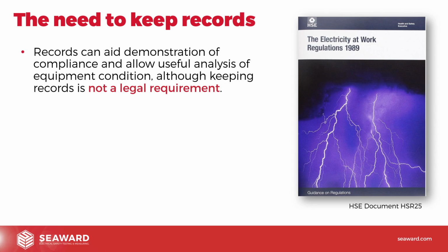The first thing that they explain is that records can aid demonstration of compliance and allow useful analysis of equipment condition, although keeping records is not a legal requirement. They're very clear about that. There's no legal requirement under the Electricity at Work Regulations to keep records of maintenance or PAT testing. The problem is that if you don't have them, as it says, they can be a useful aid in the demonstration of compliance. So if you haven't got records, how do you actually prove that you did it?